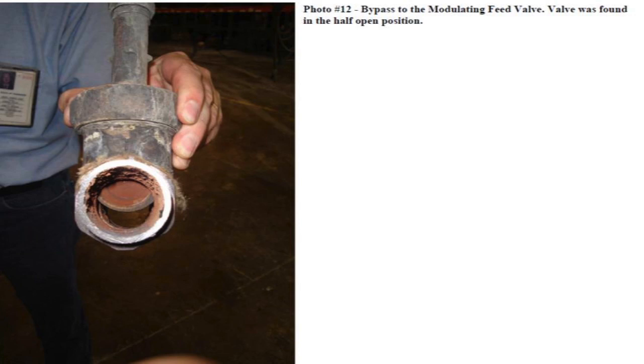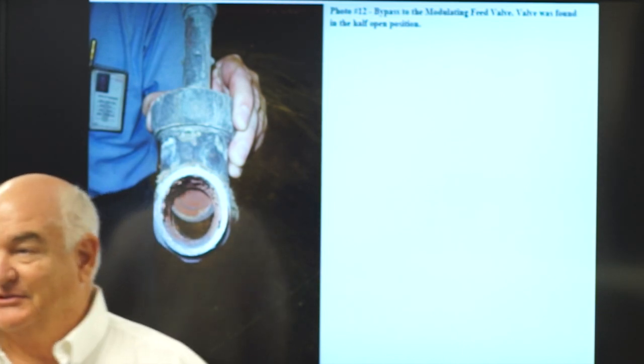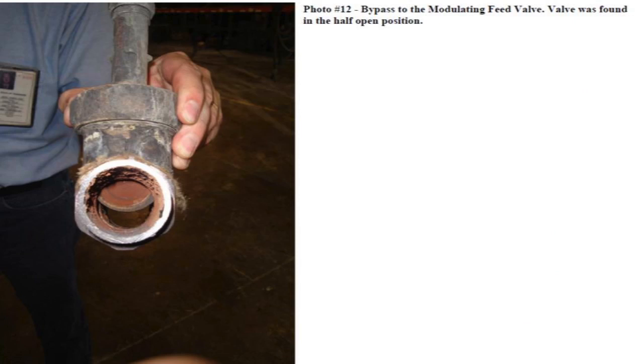And now they were just allowing as much water in as possible. About two o'clock in the afternoon, the assistant plant manager was walking by the boiler room. He heard a strange noise and walked in. His description: boiler number one was cherry red. What had happened was they had restricted the water and the boiler ran out of water. All the heat energy normally absorbed by cold water in those tubes was now being absorbed by the steel.